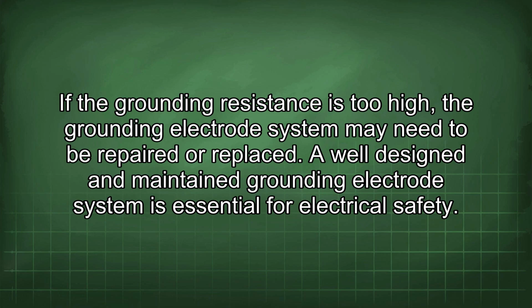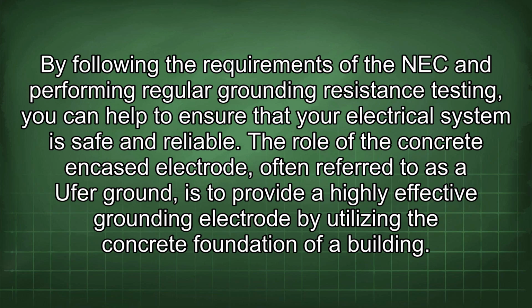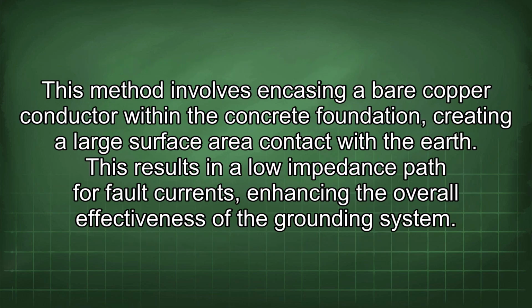A well-designed and maintained grounding electrode system is essential for electrical safety. By following the requirements of the NEC and performing regular grounding resistance testing, you can help to ensure that your electrical system is safe and reliable. The role of the concrete encased electrode, often referred to as a Ufer ground, is to provide a highly effective grounding electrode by utilizing the concrete foundation of a building. This method involves encasing a bare copper conductor within the concrete foundation, creating a large surface area contact with the earth. This results in a low impedance path for fault currents, enhancing the overall effectiveness of the grounding system.